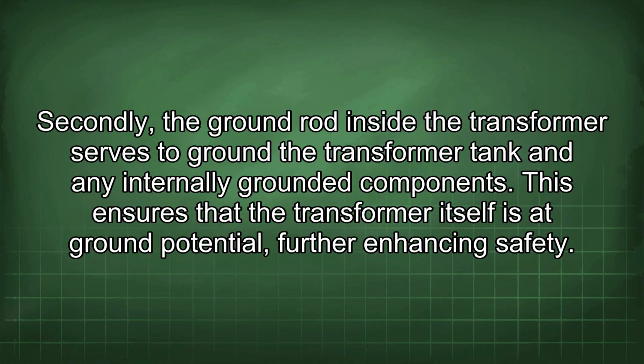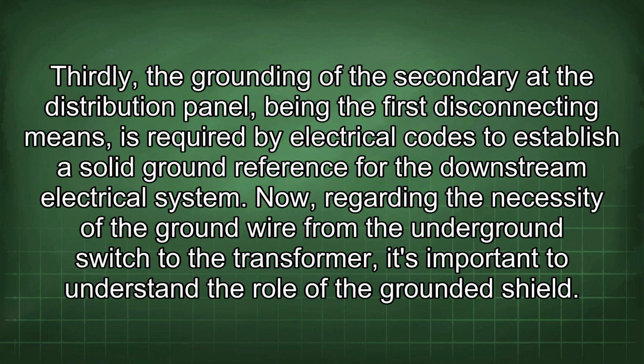Secondly, the ground rod inside the transformer serves to ground the transformer tank and any internally grounded components. This ensures that the transformer itself is at ground potential, further enhancing safety. Thirdly, the grounding of the secondary at the distribution panel, being the first disconnecting means, is required by electrical codes to establish a solid ground reference for the downstream electrical system.